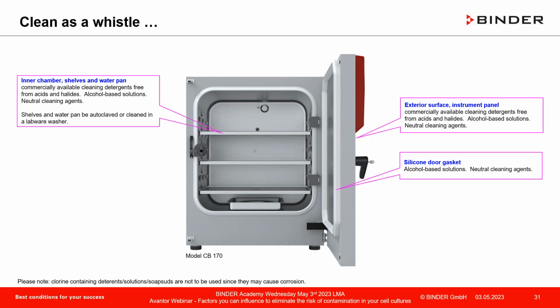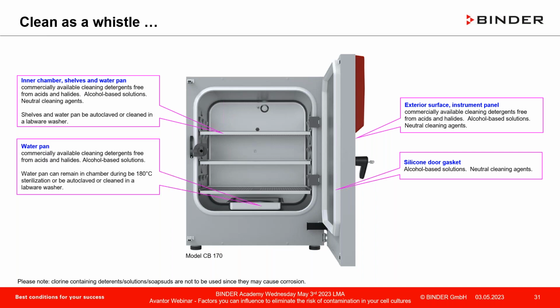Then you can go to the inner chamber. Shelves and water pans, if your autoclaves are large enough, easily placed inside. If not, they can remain inside during the 180 degrees C hot air sterilization. And if you do want to conduct a wipe disinfection, then you can once again use alcohol-based solutions, neutral cleaning agents. So that is something very, very easily done with stainless steel. Water pan, best way to do that, autoclave them or wipe disinfect them. The other alternative stays inside during the 180 degrees C hot air sterilization. Or you can even put it in a labware washer. That's also possible if you have a big one.